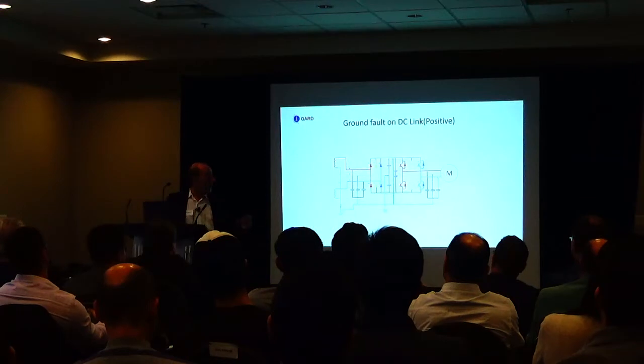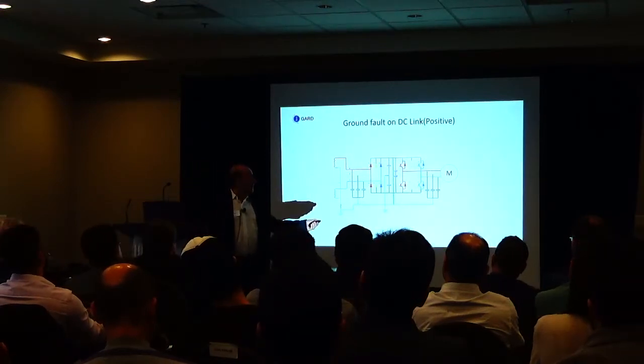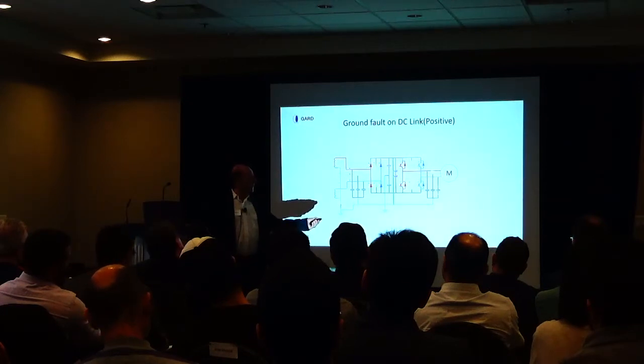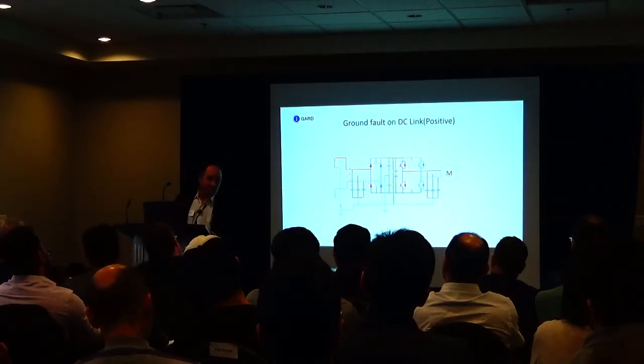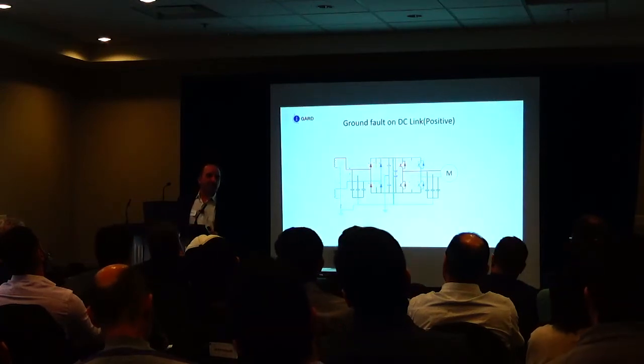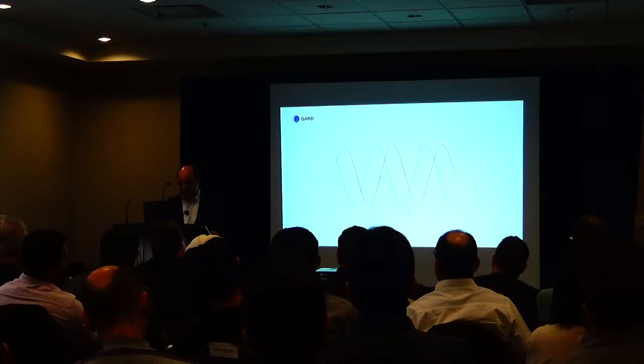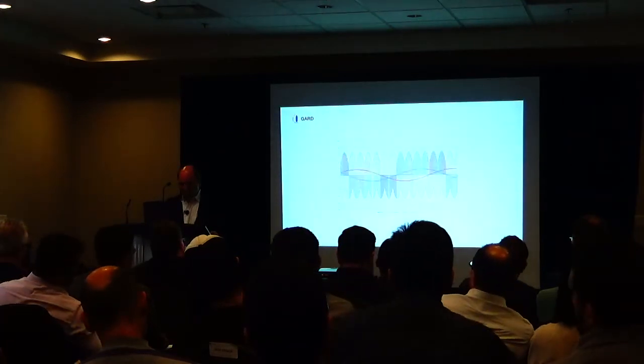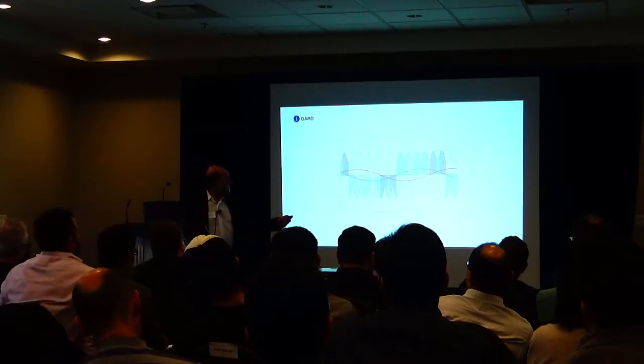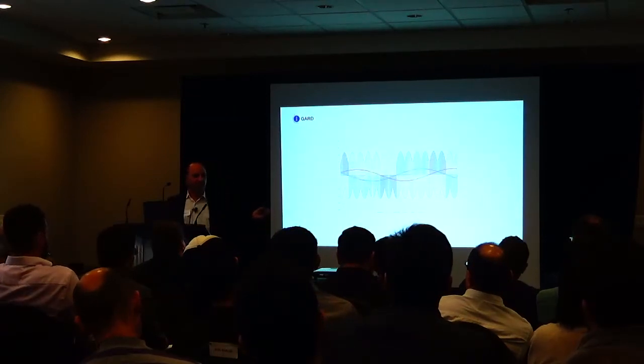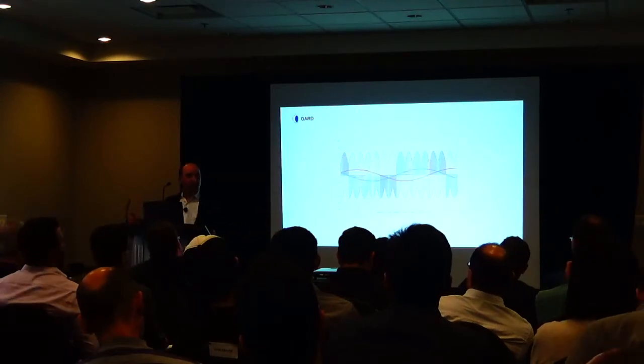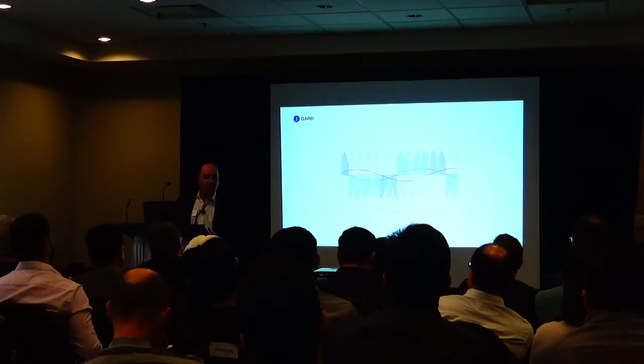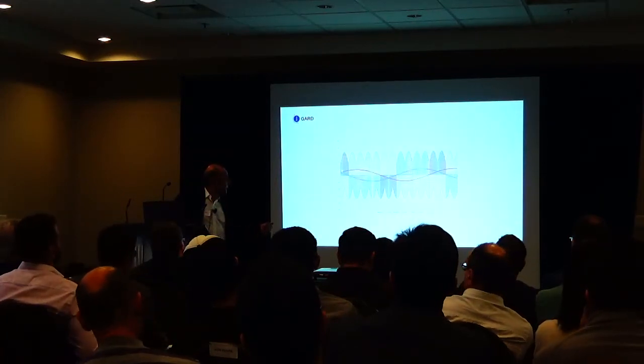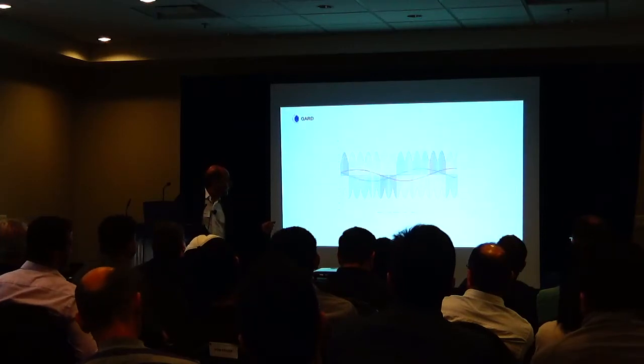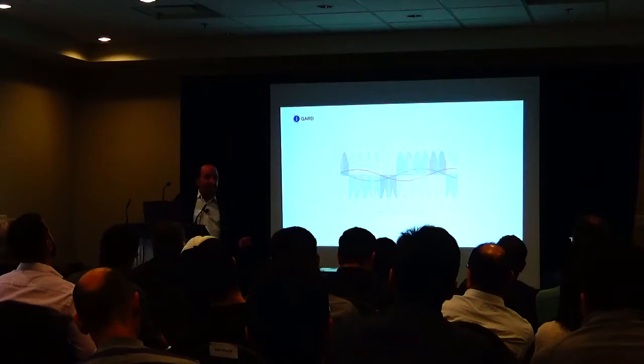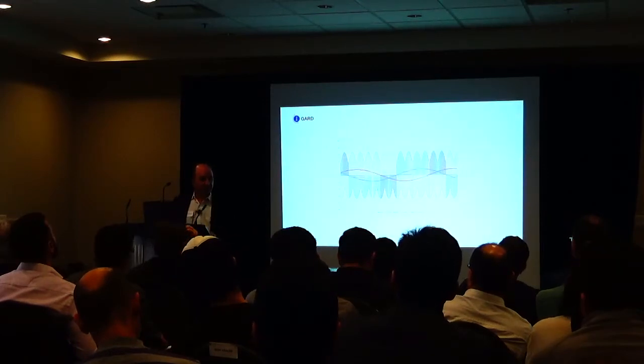One third equally. On the output, it's a little bit different, because if you have a ground fault on the output of a variable frequency drive, it depends on the speed that you're operating that motor. You could be running at, let's say, a 50 hertz fault here. There's the input, there's the output. And the output doesn't really look like this. The output is actually pulse width modulation, and the inductance of the motor makes it look like a nice sine wave. So you can see that when you have a fault on A phase, 2/3 of each phase is time shared with that fault.